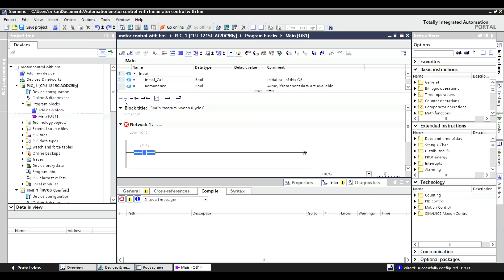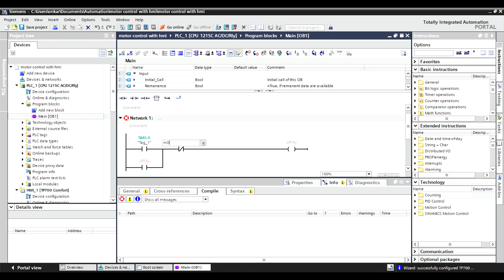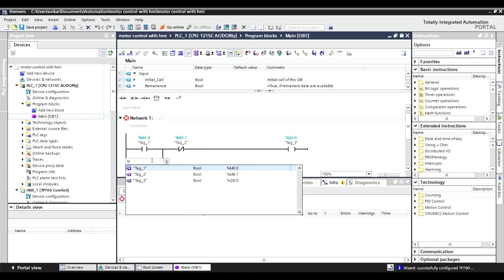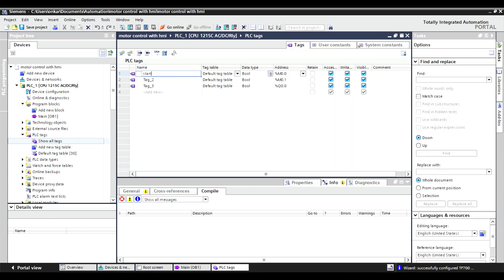Let's configure the PLC logic. Add a normally open NO contact for the start button, a normally closed NC contact for the stop button, and an output for the motor. Don't forget to add a latch circuit to keep the motor running after starting.